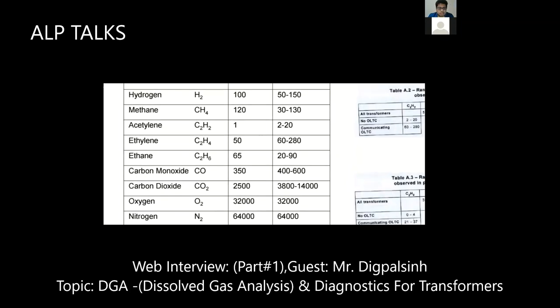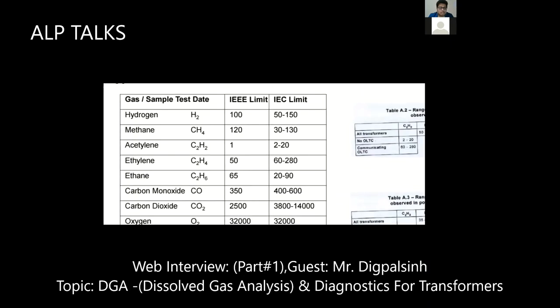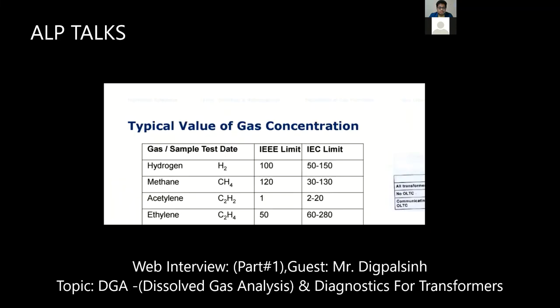Okay. Immediately, acetylene. One thing: these IEEE values, are they maximum or minimum values? It is the maximum value. If it goes beyond 120, it is abnormal. Okay, we should not go beyond that. Yeah. Okay, the value should be within the IEEE limit. Yes, that is the upper limit. Yeah, that is the upper side limit.